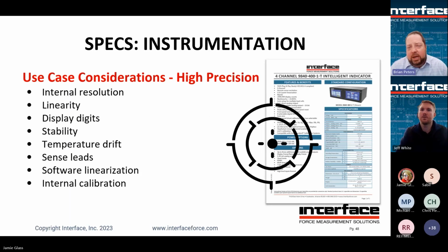So let's look at now if you need a very accurate, very precise measurement. Well, now you're going to start shifting to looking at internal resolution with priority, perhaps. What's the linearity of the device? How many display digits do you actually get to see on that? Stability, drift, those start to come into the picture. Sense leads is a 6-wire, like Jeff was talking about earlier. That's a huge benefit if you've got long cable runs, for example, to ensure that the instrumentation is taking into account any signal loss over that long cable run.